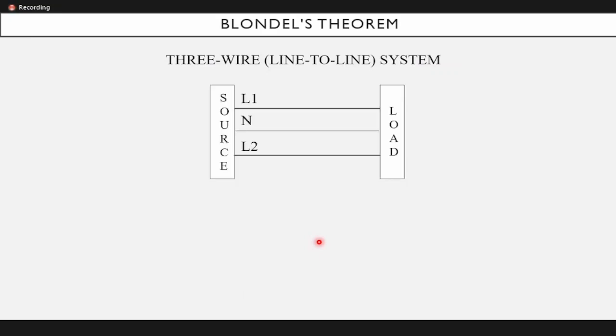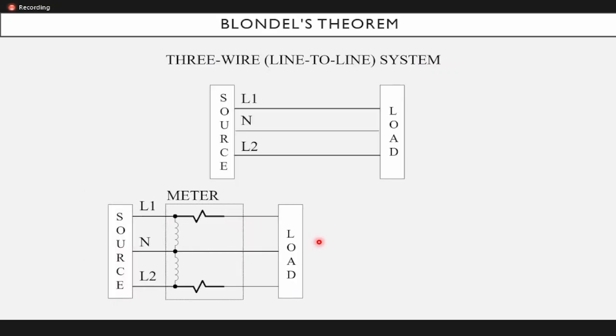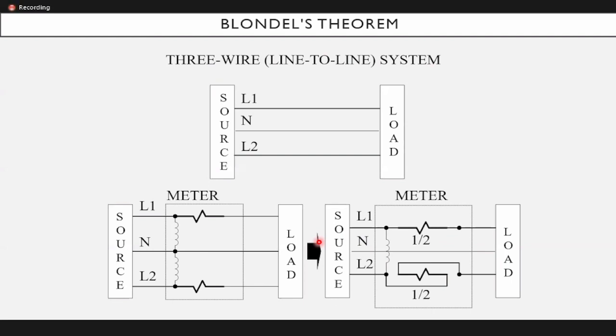This is the line diagram of a single phase three-wire system or a line-to-line system. This is the most common single phase residential connection. The potential coil is connected across line one and line two, while the current coil is connected in series with line one and line two. For this, the current coil measures 50% of line one and 50% of line two, with a total of 100% line current measurement.